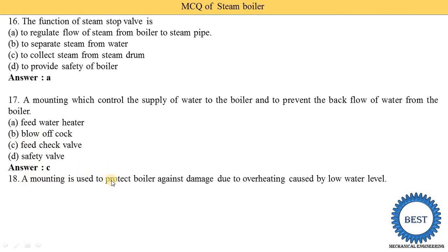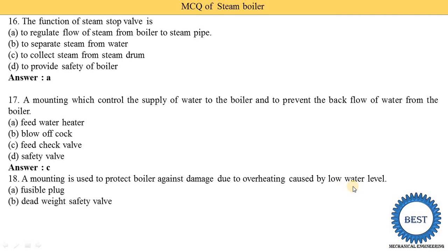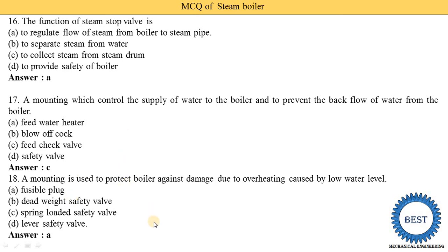Which mounting is used to protect the boiler against damage due to overheating caused by low water level? Option A — fusible plug — is the correct answer. When heating increases, the fusible plug melts, water is supplied to the furnace, and the fire is stopped, thereby avoiding overheating of the boiler.